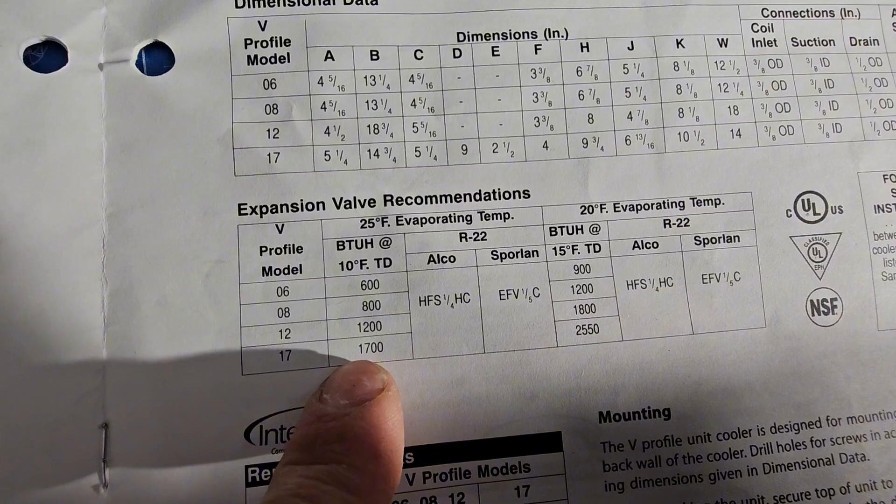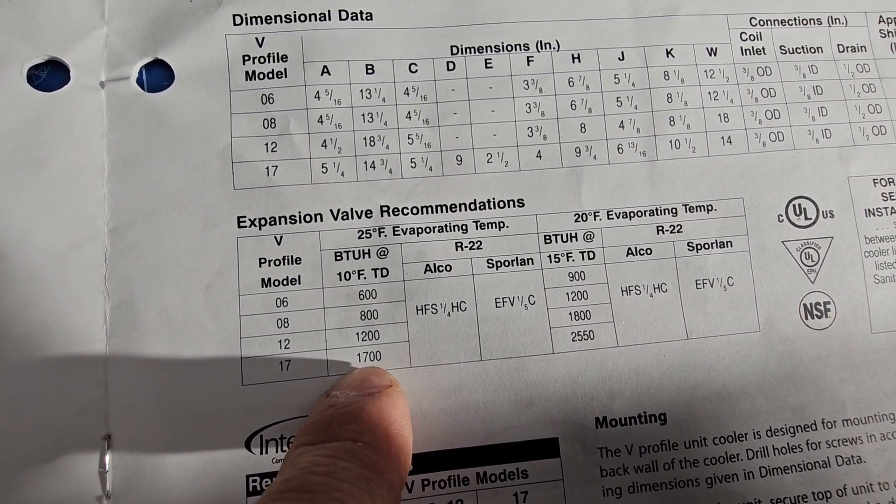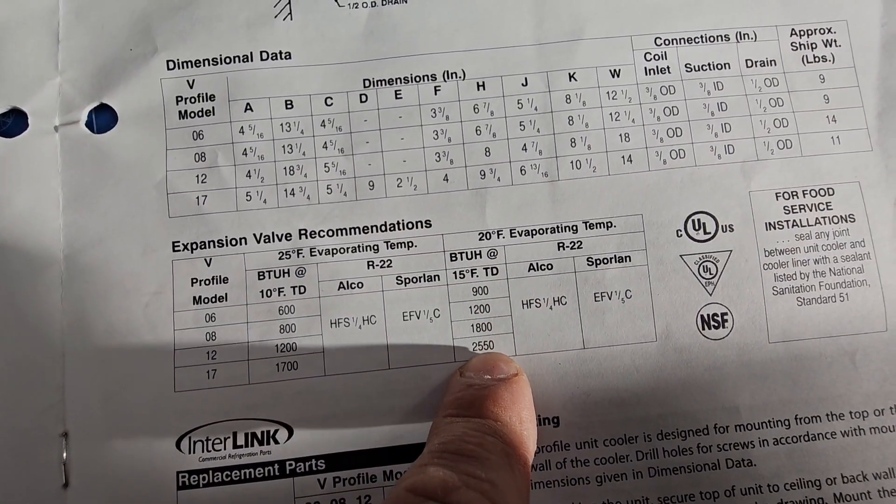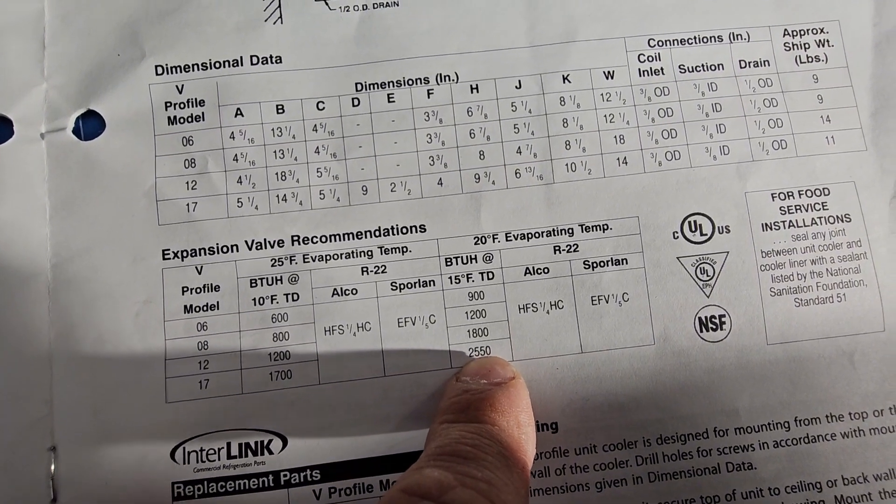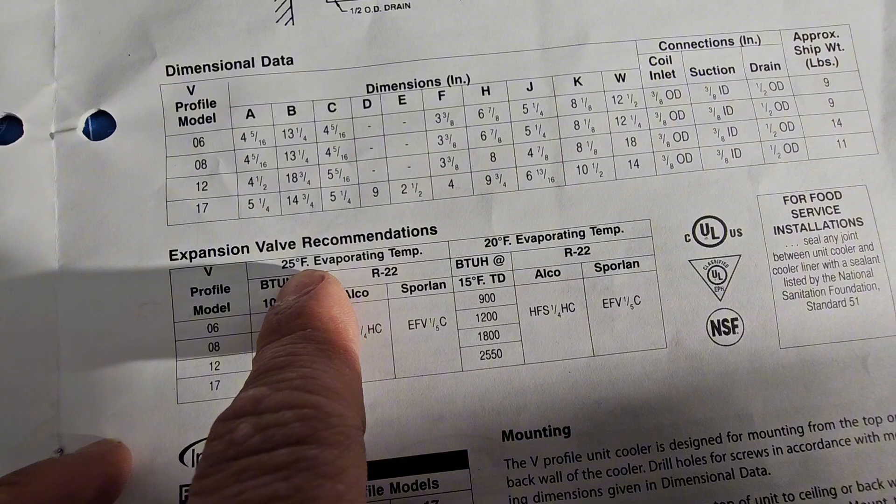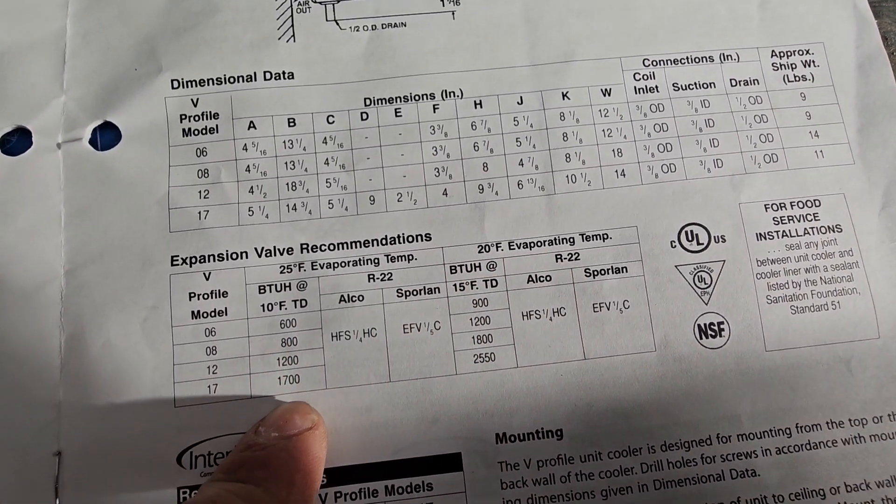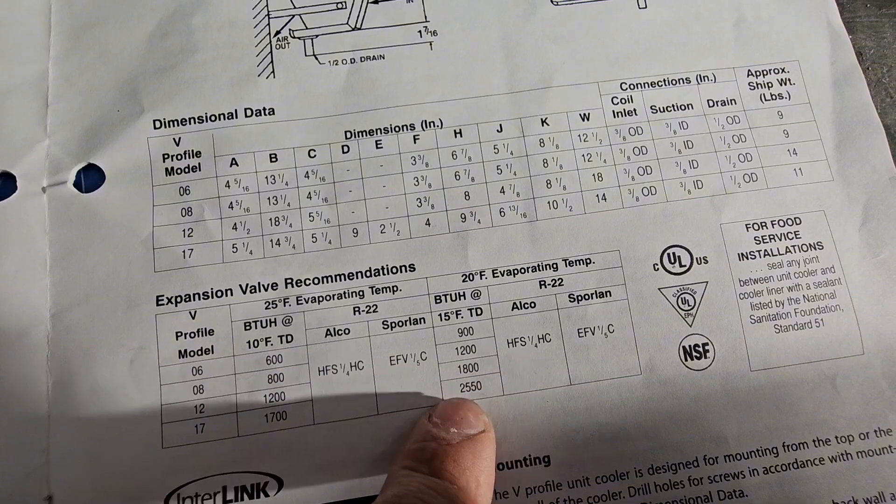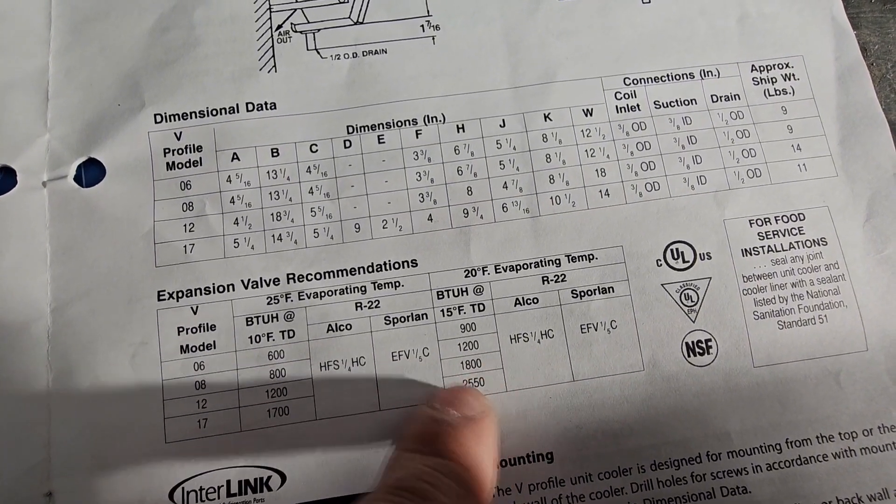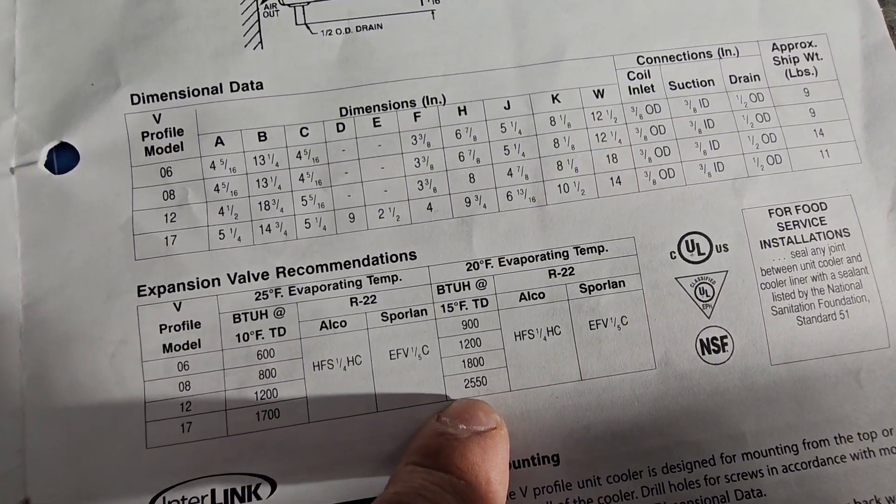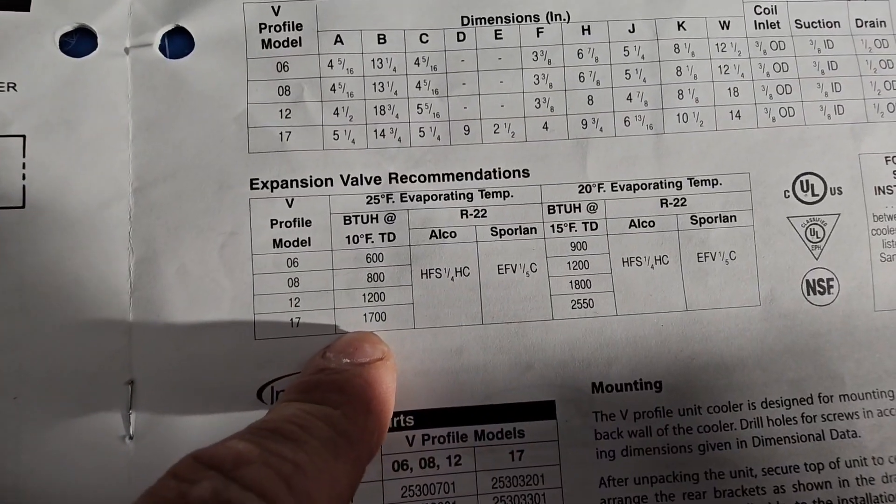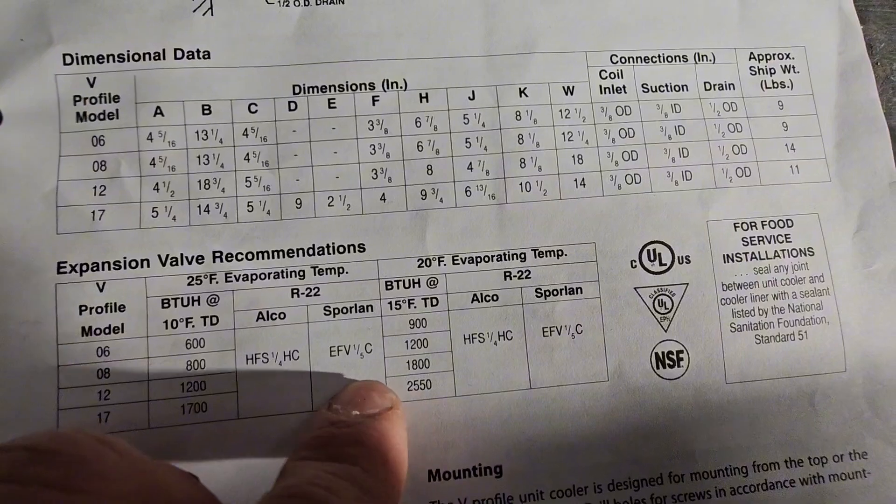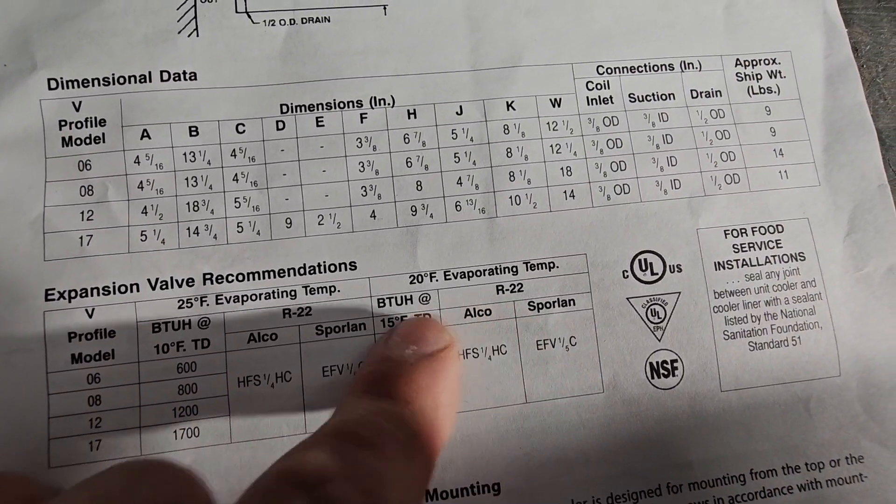And as you can see, at a 10 degree TD it gives you 1700 BTUs. At a 15 degree TD it gives you 2550 BTUs. Basically that's a 25 degree evaporator, that's a 20 degree evaporator. And basically what this means is what you have for a compressor. So if you have a strong compressor it's 2500, if you have a little bit of a weaker compressor you get 1700 BTUs out of this coil.